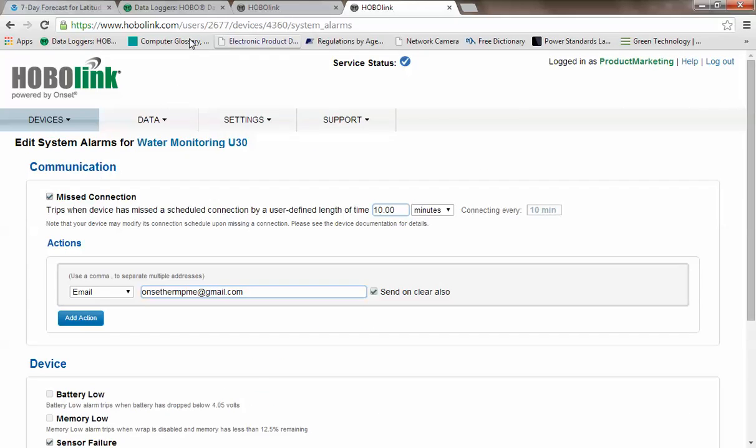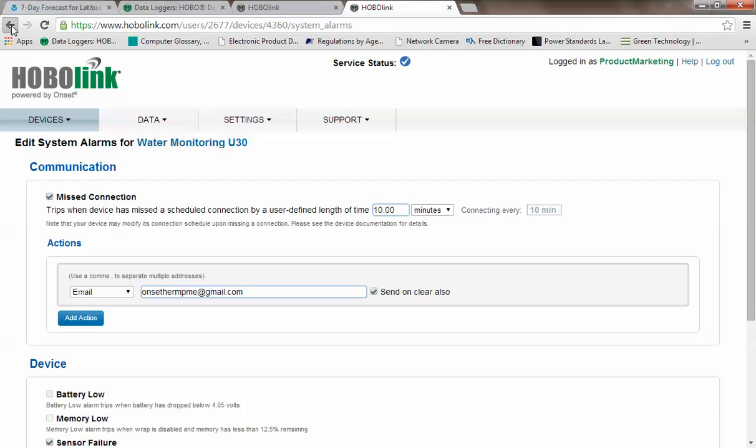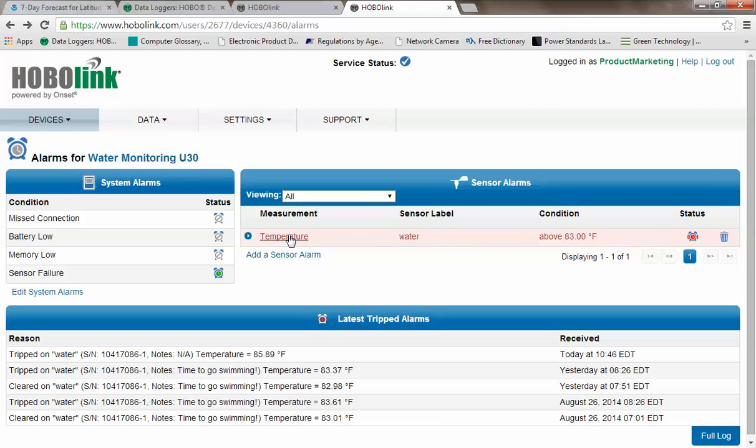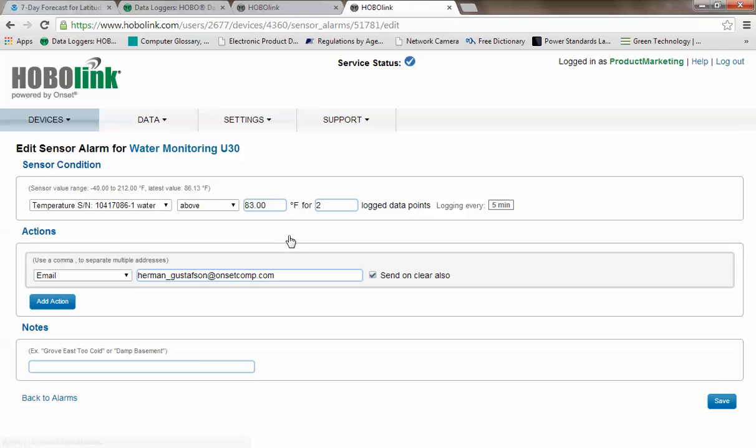If we back up to the main alarm page, we can see now we can show how to set up sensor alarms. Currently, we just have one on temperature and the sensor label is water. Let's see how this is configured. We click on the measurement type and it opens that sensor alarm page. We can see that this specific sensor is set to give us a high alarm above a threshold of 83 degrees for two log data points. And we're logging every five minutes.